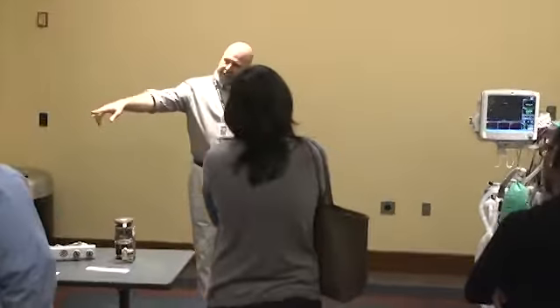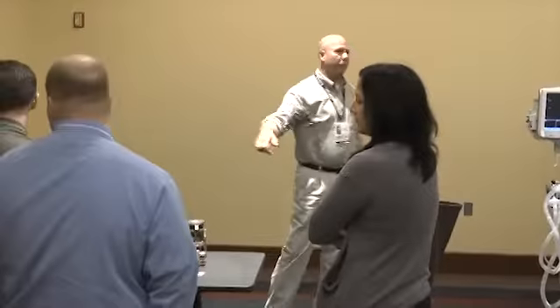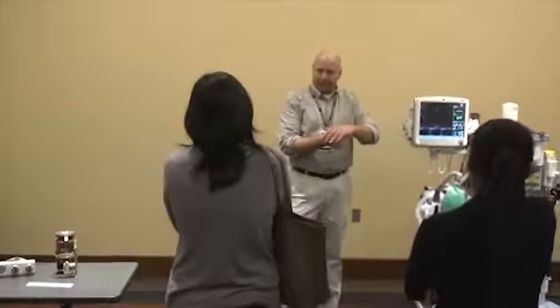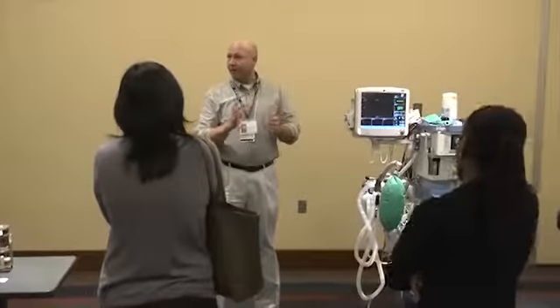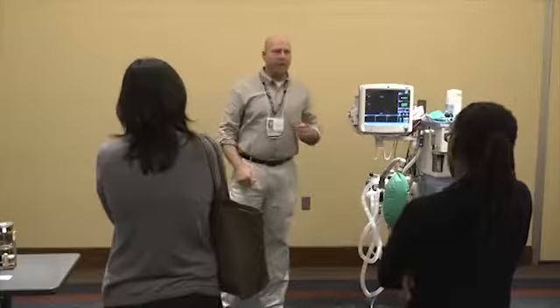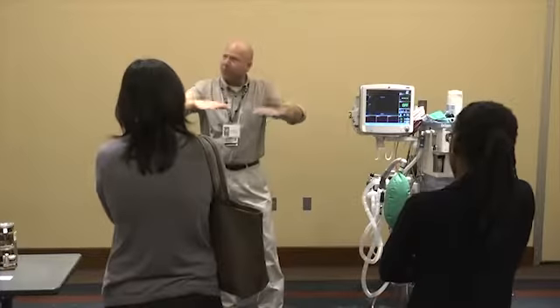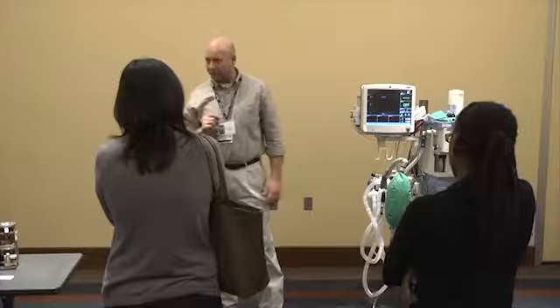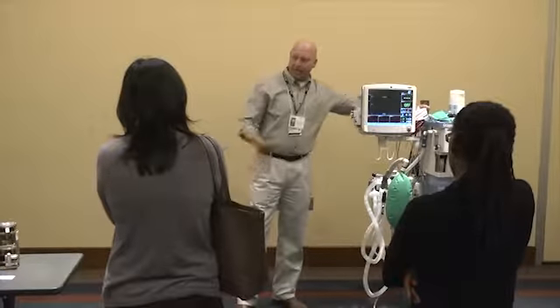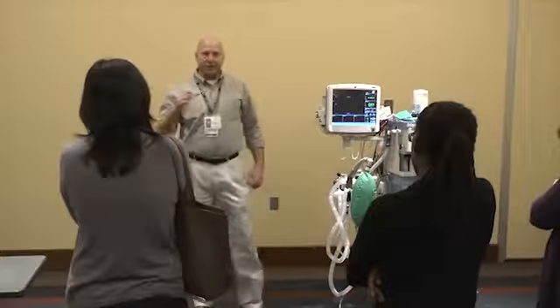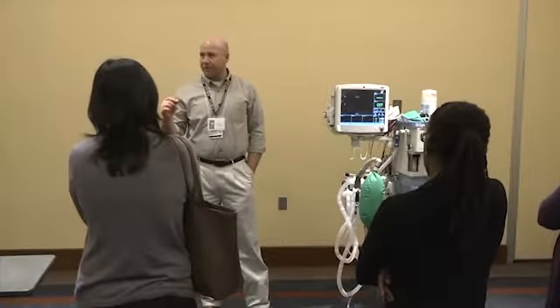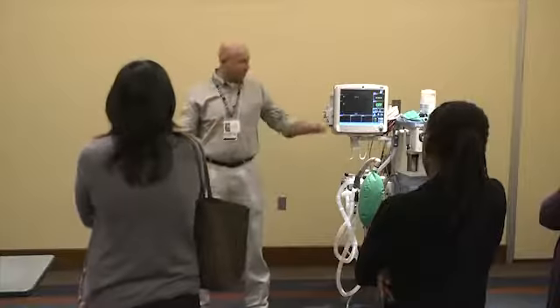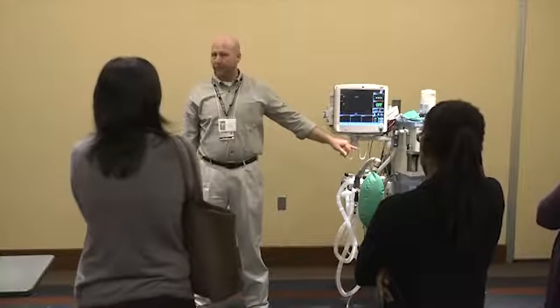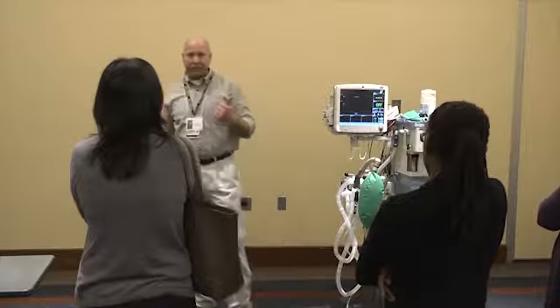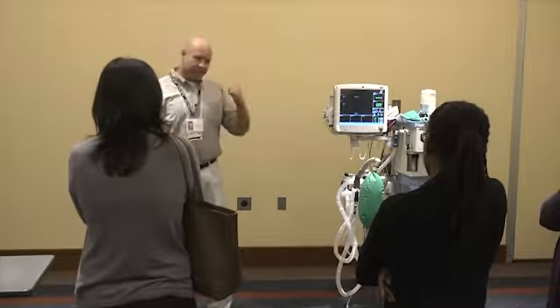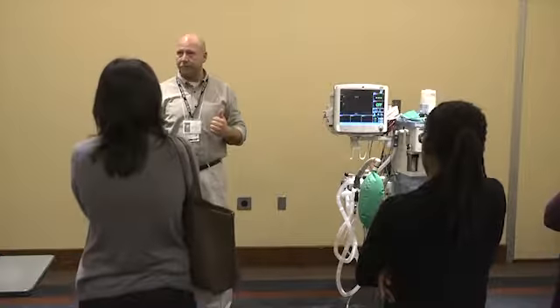All it is, it works on a diaphragm similar to the oxygen ratio controller. You have pressure on one side hitting this diaphragm, keeping it open, allowing N2O and air to flow. When you lose your oxygen pressure, those diaphragms close, and you start losing all your other gases as well on the older machines. The newer ones, the Apollos, Fabius series, they actually only have an OFPD for the nitrous. That way, if you lose oxygen, you'll lose your nitrous, but you'll still have your medical air.